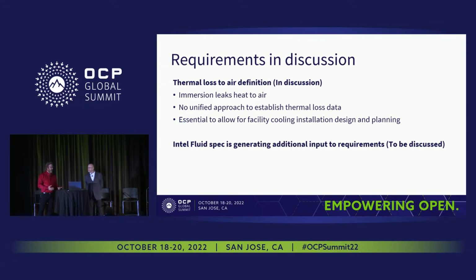So what we're looking at now is how do we quantify that thermal loss to the air environment, and how do we come up with methods every tank provider or manufacturer can include in their process to verify how much thermal load is being lost to the air. That's necessary to help with facility planning, because even with a liquid cooling setup, it still warms up the air, so you need some air treatment, and it needs to become quantifiable, basically a specification for the product.